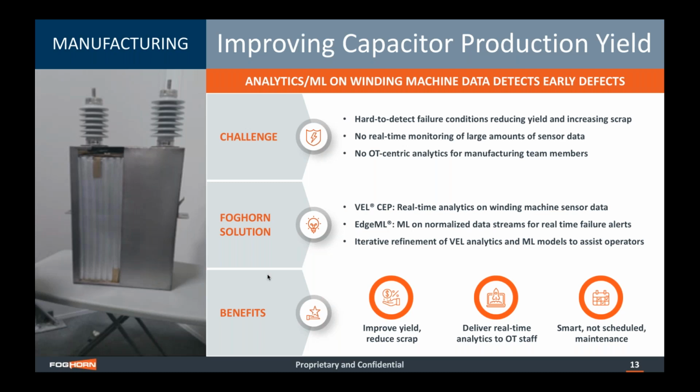Unfortunately, they couldn't do anything. It's beyond a certain point. So what we did is, for example, this capability or the technology that I described, we installed it on a little gateway like a Raspberry Pi, connected to all of the sensors from the winding machine, because the customer wasn't sure whether the failures were occurring during the winding phase, treat oven phase, or the last phase. What we actually showed them is that the failures were actually caused at the very first stage itself.